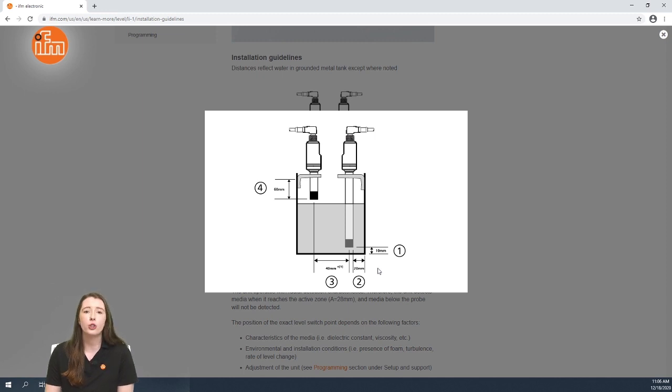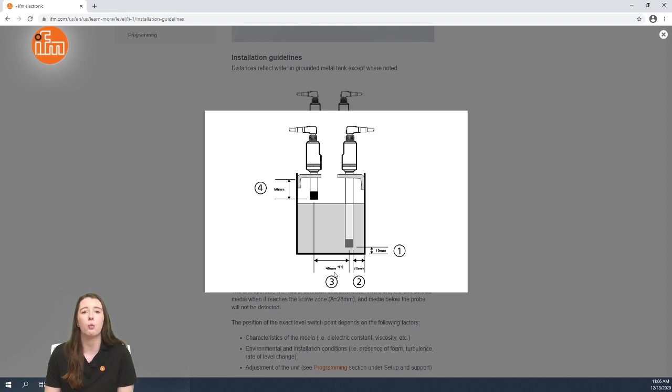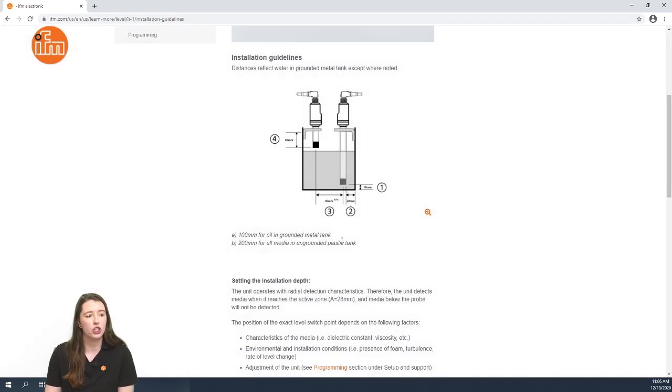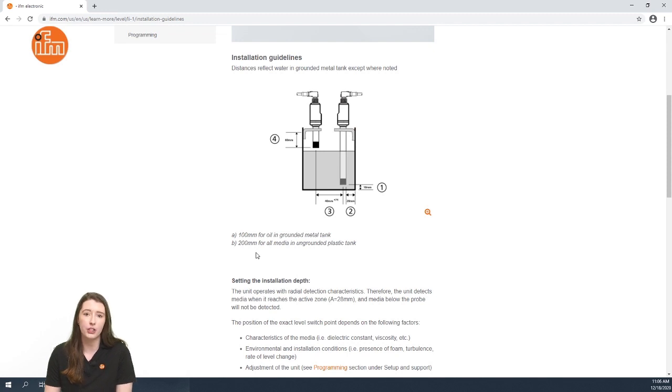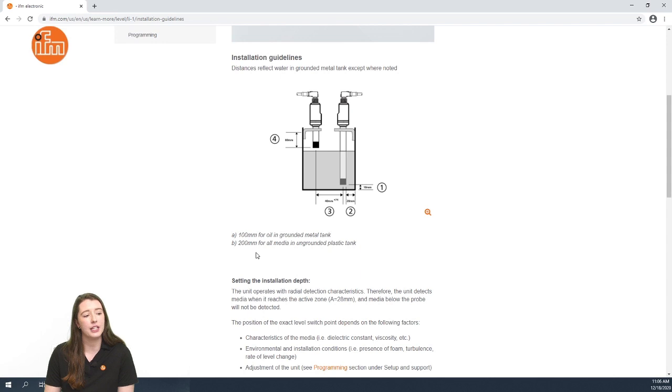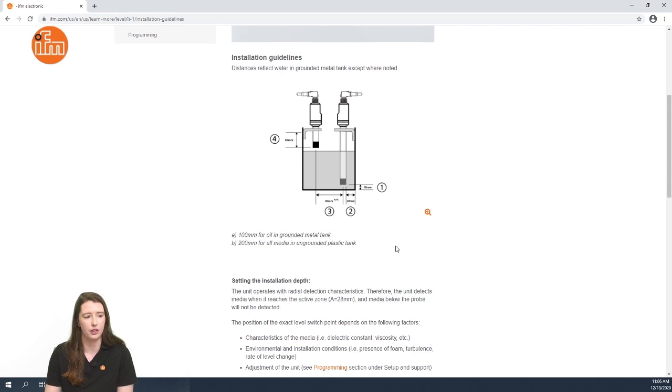If you have two LI sensors mounted in one tank they must be at least 40 millimeters away from each other in a water application where the tank is grounded. If the application is oil media in a grounded tank the two LI sensors must be at least 100 millimeters away from each other, and in an ungrounded plastic tank the two LI sensors must be at least 200 millimeters away from each other.